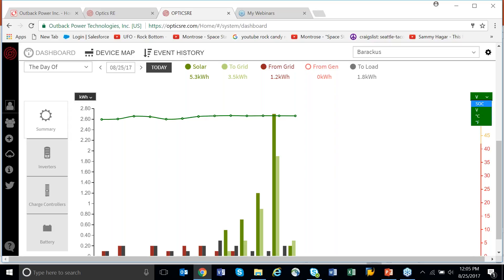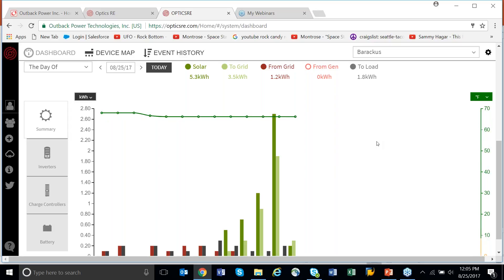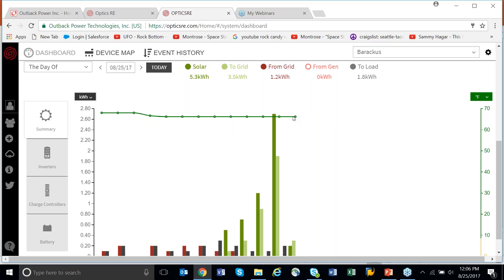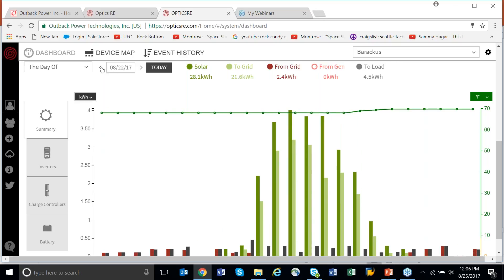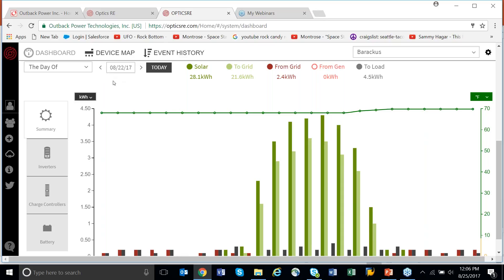If you come down and click on temperature, it tells you the high and low within each time frame — usually about an hour. This is important: right here you could save a customer from having to physically go look at the battery. I can go back and look at temperature over time — did my batteries get exposed to anything super hot or super cold? This is information from the temp sensor that you plug into port one; it shares that temperature with all of the equipment in the system.